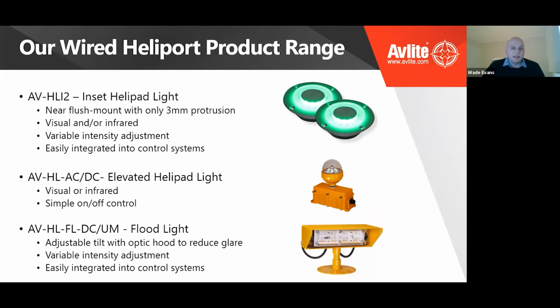That's complemented for elevated fixture applications with our HL, an AC or DC fixture. It's visual or infrared, not both, with simple on-off control. This is designed around hard-mounted applications where inset fixtures aren't viable, where the coring or actual civil works aren't suitable, so you move on to an elevated fixture. It doesn't have as many control and monitoring features since it's simple on-off, but it meets the need when you must bolt the fixture onto a deck to meet the elevated requirement without penetrating the helipad itself.